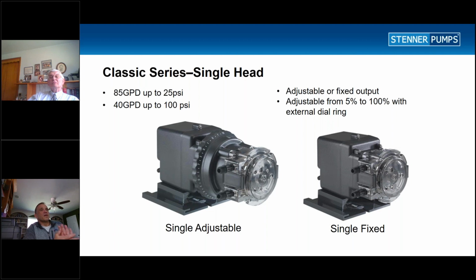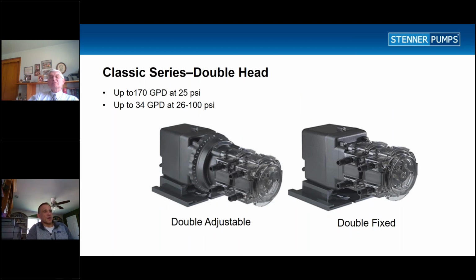When we look at the 2 pumps, we have some customers that will go to a fixed output pump and operate the pump at max flow and just turn it on and off depending on the flow switch, but then they'll adjust the flow rate based off the tube. And then here we show our classic adjustable in the double head version. Most people in the water conditioning market are going to tend to stick with a single head pump.